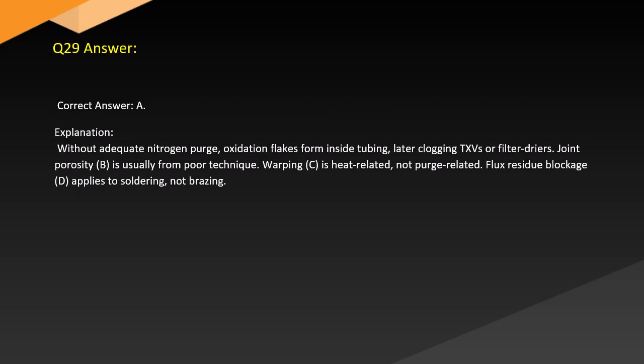Answer. Correct answer: A. Explanation. Without adequate nitrogen purge, oxidation flakes form inside the tubing, later clogging TXVs or filter dryers. Joint porosity, B, is usually from poor technique. Warping, C, is heat-related, not purge-related. Flux residue blockage, D, applies to soldering, not brazing.